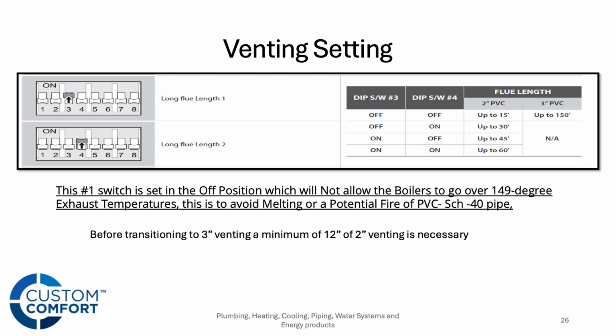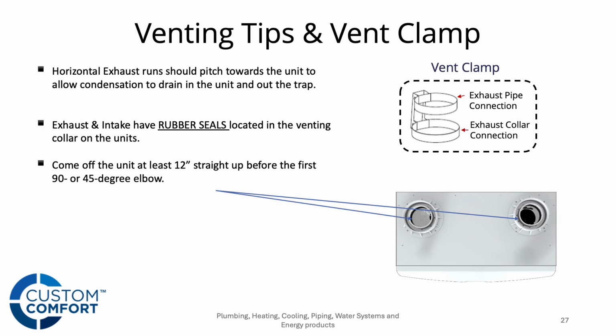And again, talking a little bit more about venting, if we are going to vent in 3-inch, we want to see at least 12 inches of straight 2-inch off the top of that boiler before making any type of transition to 3-inch or a 90, 45, anything like that. So 12 inches off the top of 2-inch before we put any type of fitting on there. On top, the vent connections have rubber gaskets on both the inlet and the exhaust. Those vent clamps that I mentioned before come with the boiler. That's how you're making a connection of the vent material to the boiler itself.